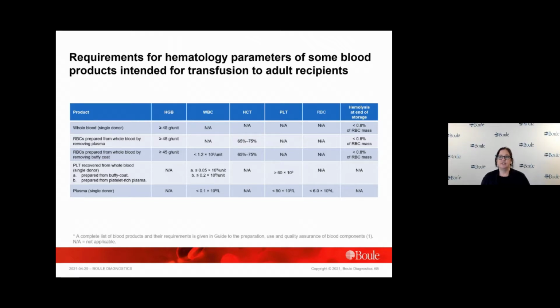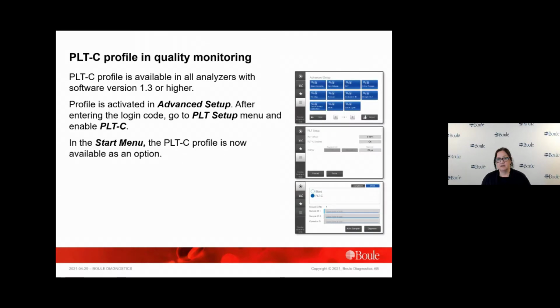Hematology testing is commonly used also in quality monitoring of the blood products. For example, platelet concentrates are typically assessed for residual leukocytes, and red blood cell products are additionally assessed for hemoglobin and hematocrit values. The blood bank application resides in the Medonic M32 analyzers as a special analysis profile. The factory default blood bank profile is named PLTC, as in platelet concentrate. The profile is pre-installed in the instrument and can be activated by the service technician upon delivery of the system.